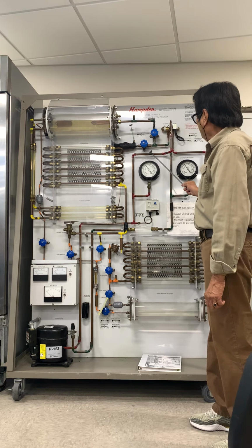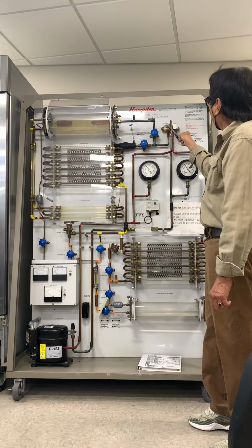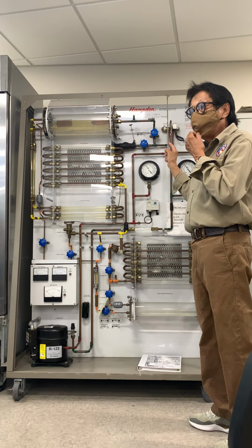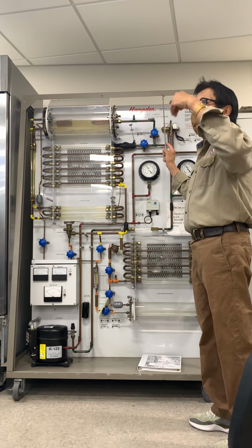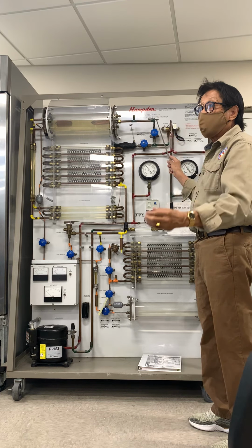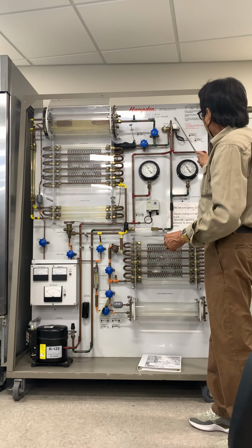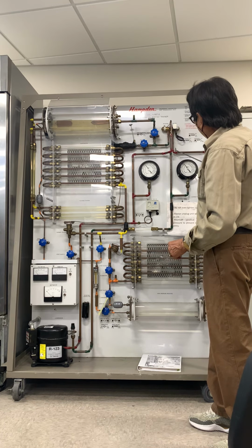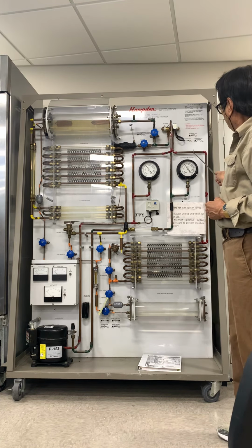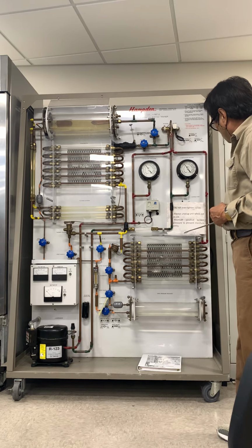From there, it would leave and move upwards, and it would hit this component called the reverse cycle valve. I will explain the reverse cycle valve purpose when we reach the right point. Just to explain the refrigerant flow, we would bypass this for now. From here, it would enter the reverse cycle valve and come out here as an outlet. Just follow the red painting. It would still be high pressure, high temperature gas coming down.